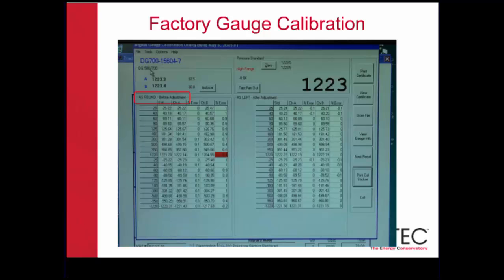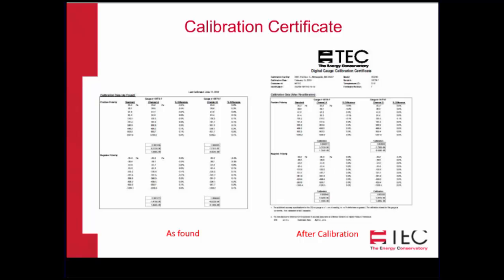So there's the as found, the before adjustment. There's the numbers after adjustment. And this is the calibration certificate. It's a little blurry, can't see it too much, but every person gets a calibration certificate with their gauge new. And when you have it calibrated, you will get 2 sheets of paper. The one on the left is as found, and the one on the right is after calibration.